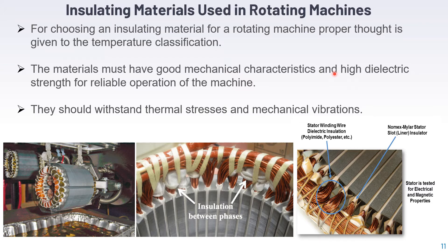Insulating materials used in rotating machines: rotating machines are generators and motors, which by construction have two parts — stator and rotor. Either on the stator or rotor there will be winding to carry current or produce EMF, and the other part will have poles or magnetic path. For choosing an insulating material for a rotating machine, proper consideration must be given with respect to temperature classification. The materials must have good mechanical characteristics and high dielectric strength for reliable operation, and should withstand thermal stresses and mechanical vibration.